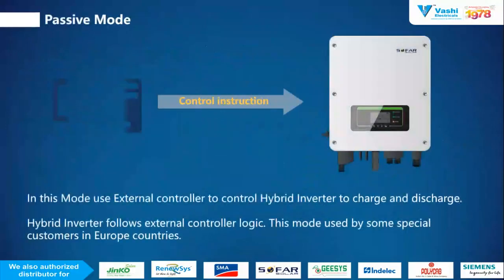In the passive mode, the hybrid inverter functions the same way as in the other modes you described. In this mode, an external controller is used to control the hybrid inverter to charge and discharge. It means you can remotely control the inverter for charge and discharge. You can easily monitor remotely, or change some parameters for the charge and discharge. So the hybrid inverter follows the external control logic.